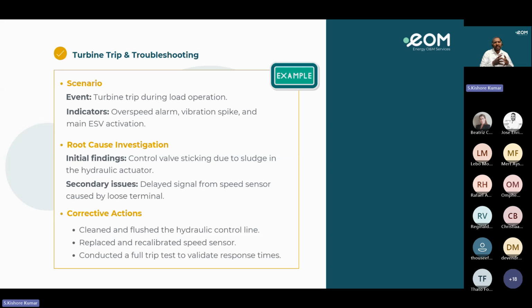And also the ESV activation. Sometimes we have to check whether the ESP is activated or not, because during turbine trip conditions, if the ESP is not activated, there is a chance of over-pressurization in the turbine chest. For that, we need proper training of operators for quick diagnostics during a trip event, and also regular checks of the instrumentation and the sensors. It is essential.